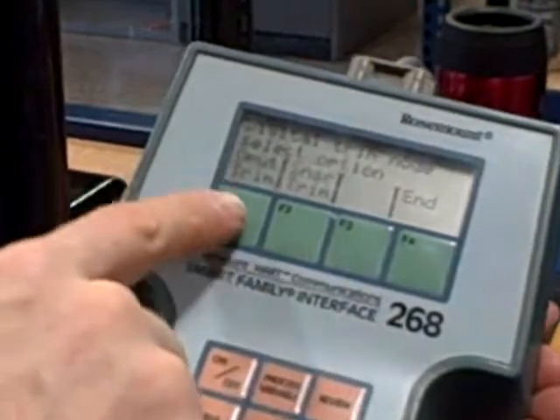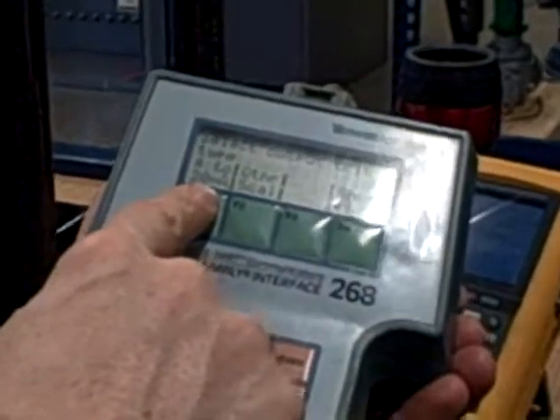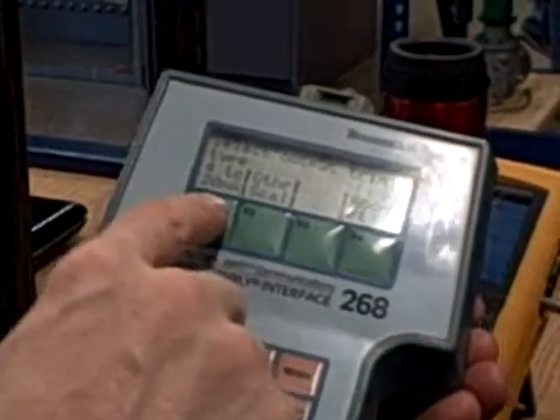I want to now do an output trim. I'm going to trim the D-to-A converter on the output of that transmitter. So I hit the output button. Select the output trim type. You want 4 to 20 milliamps or some other scale? Well I want to do 4 to 20 milliamps.